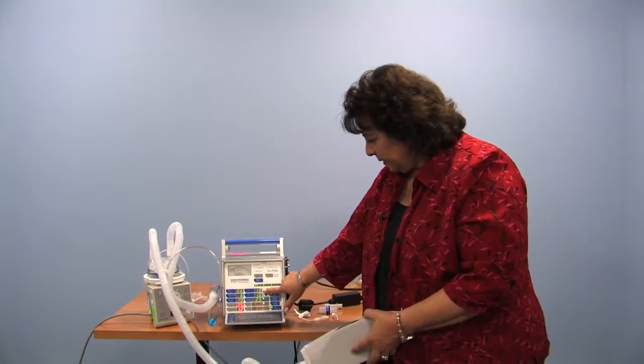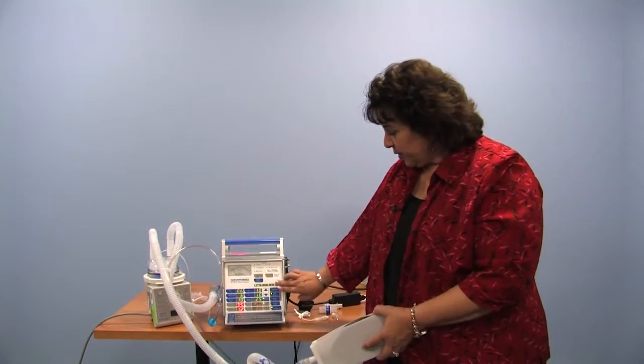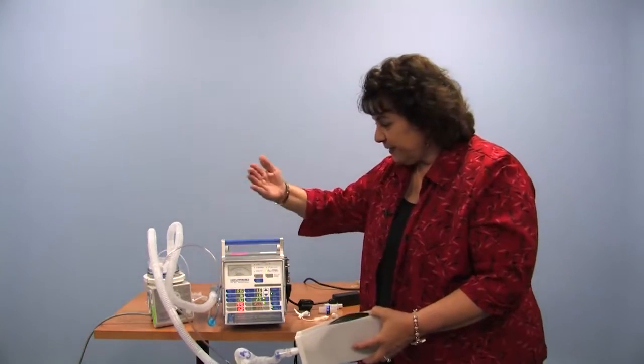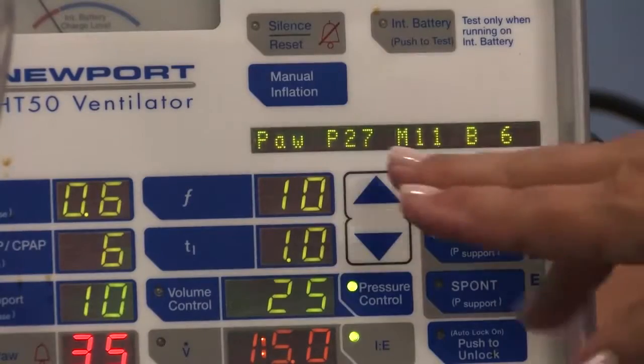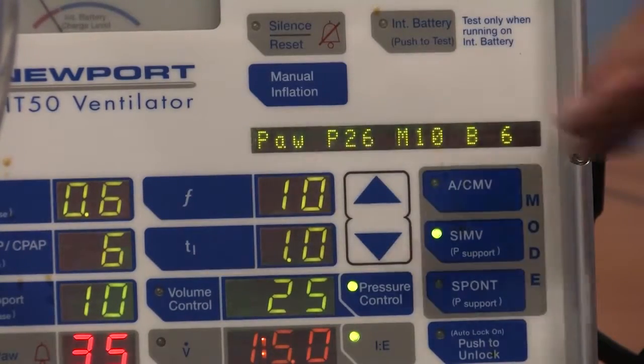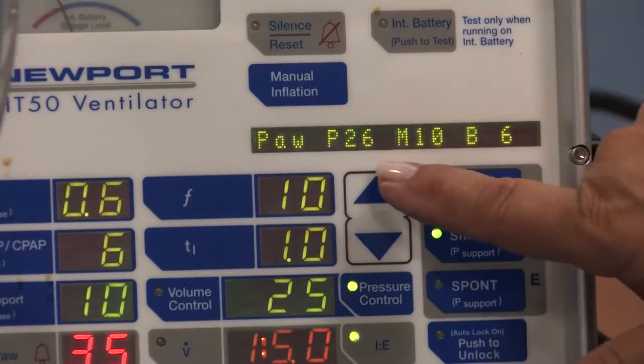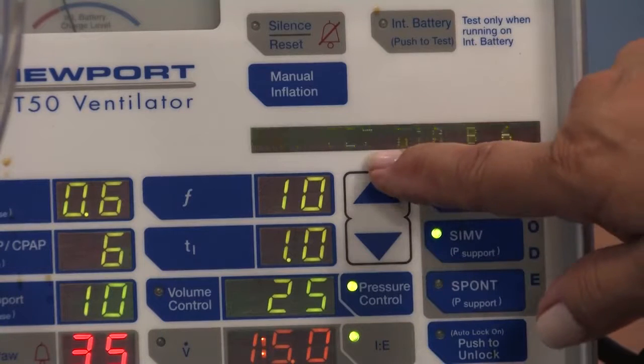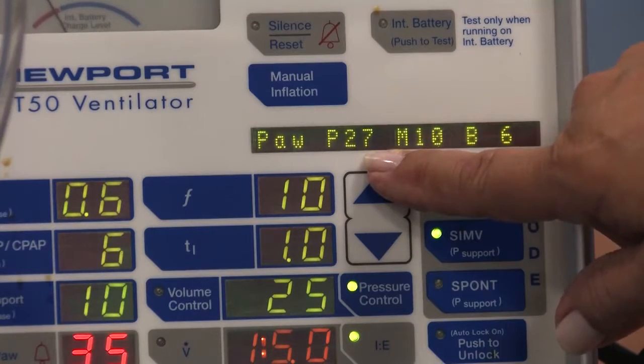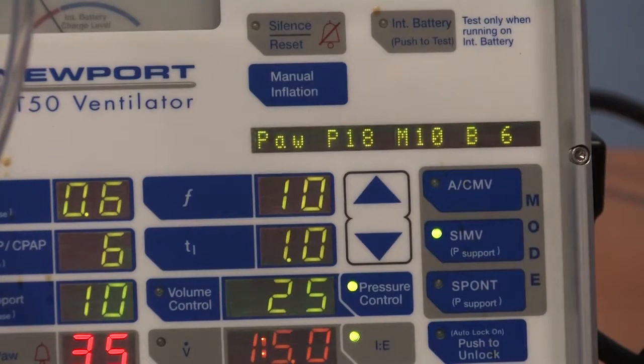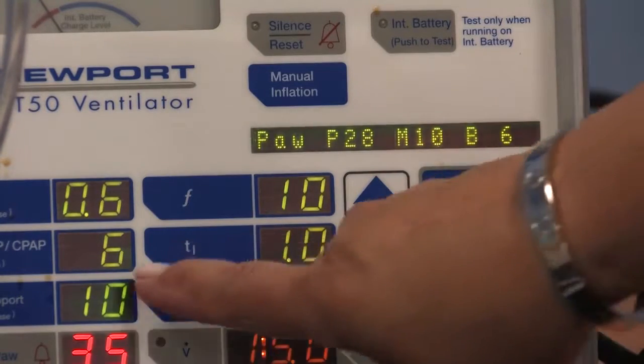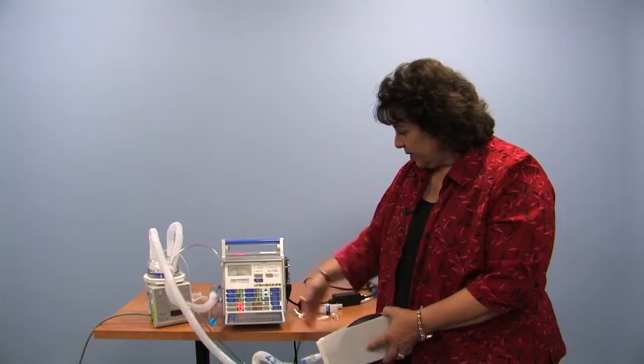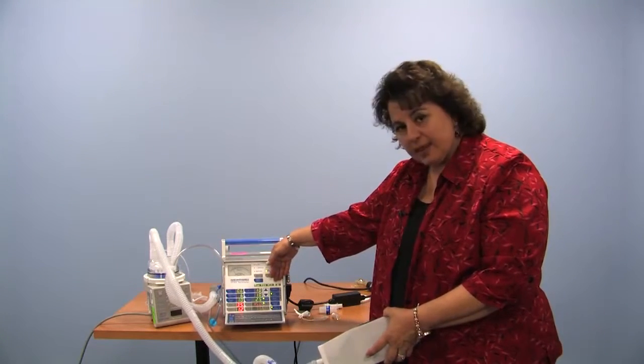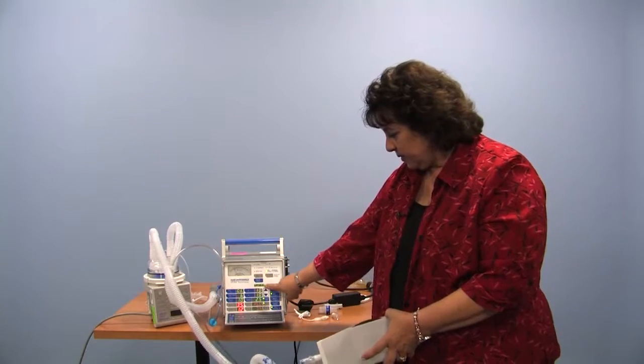I can push the up arrow again, and I have a choice of pressures that I can look at. So we have 3 screens here that are being information fed back from the hoses to the machine. We can look at the pressures, we can look at the volumes and the breath rate. We can have it blank if we so choose. Right here we're going to see the pressure, which is, we've asked for 25, it's measuring 26, 27, that's within range. The mean pressure tells me overall how much support this machine is providing for your child. Nothing for you to set or adjust. And then we have our baseline pressure, or PEEP, which is set here. It's set at 6 and it's measuring 6. So we have the peak pressure, the mean pressure, and the baseline pressure. This one we've set, and that's the measurement.